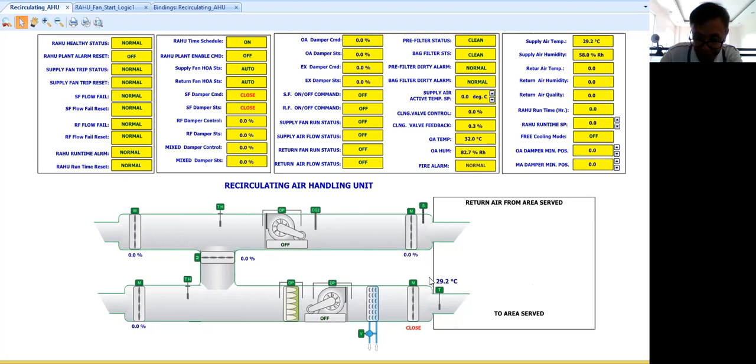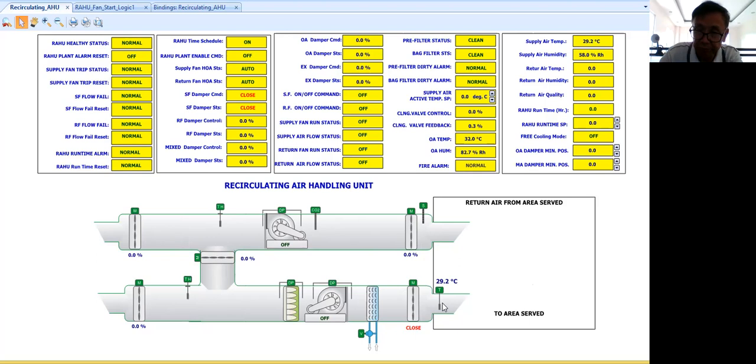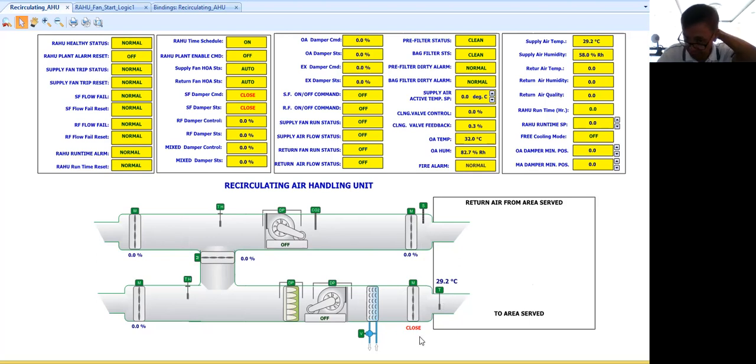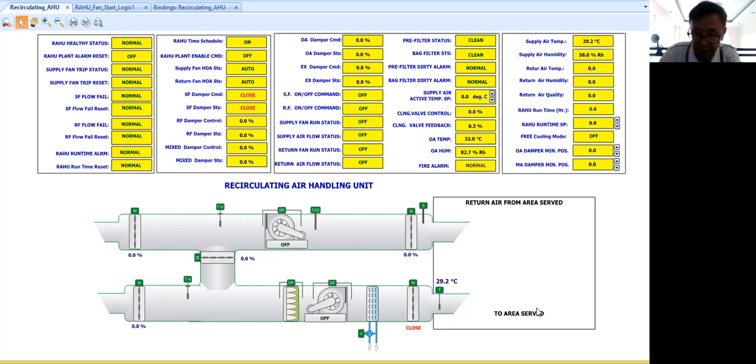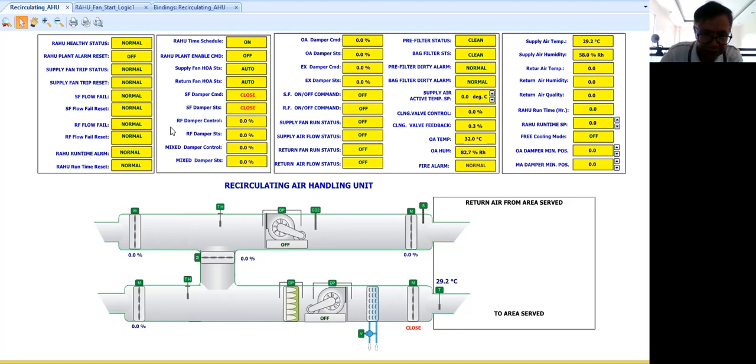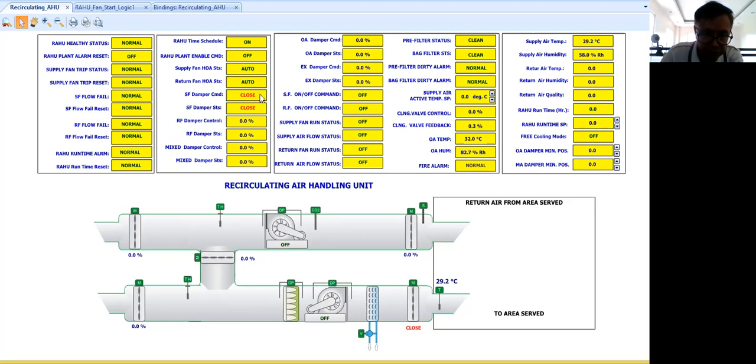Now today's scope is to simulate the initial starting of the air handling unit by starting the supply fan and return fan, but make sure some of the dampers will assume certain position to make sure that we will not overpressure our air handling unit. So when this one starts air will go out of the air handling unit.